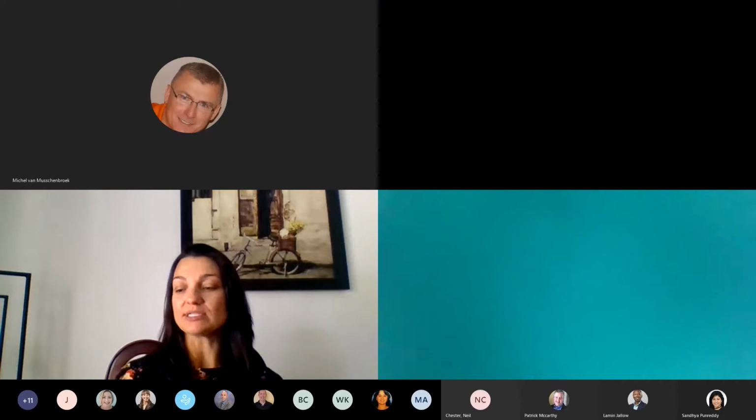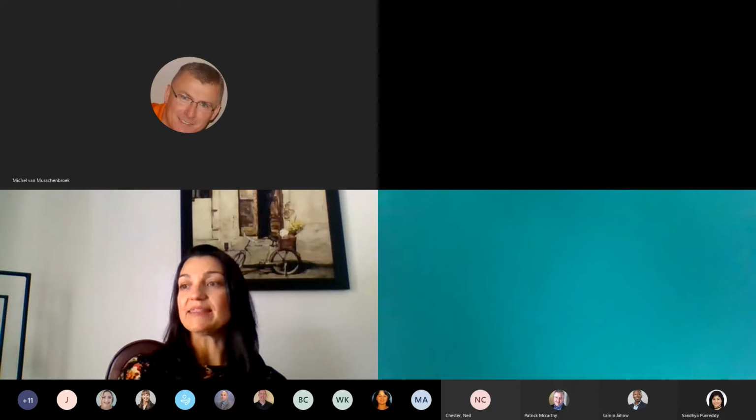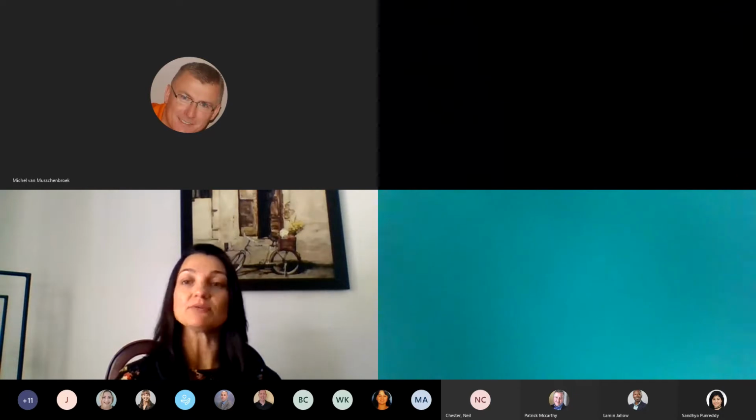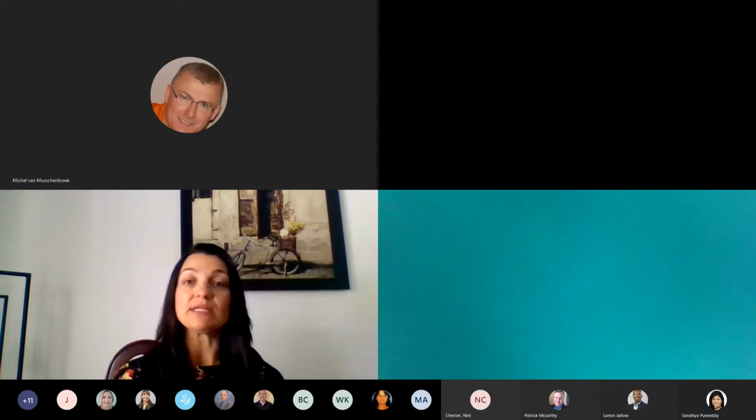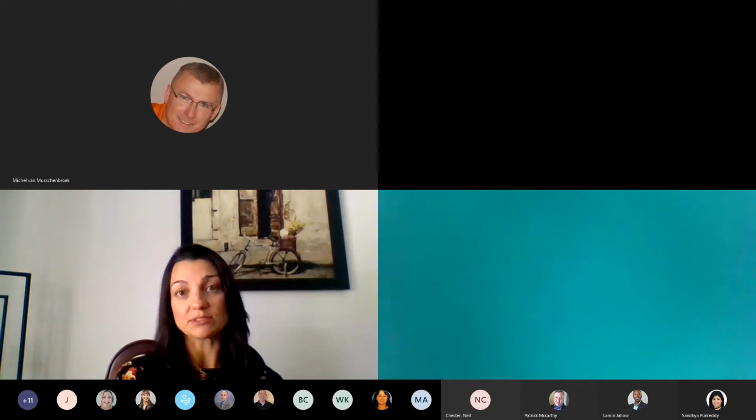So the qualification is just the specific tests that you check. For example, on an instrument, you press the start button, you want to make sure that it starts. You say that it will filter 100 mils, you want to make sure that it filters exactly 100 mils, that everything is within its predetermined acceptance criteria, and a series of those qualifications will form the validation. Those are pretty much the tests that you do, the test results.